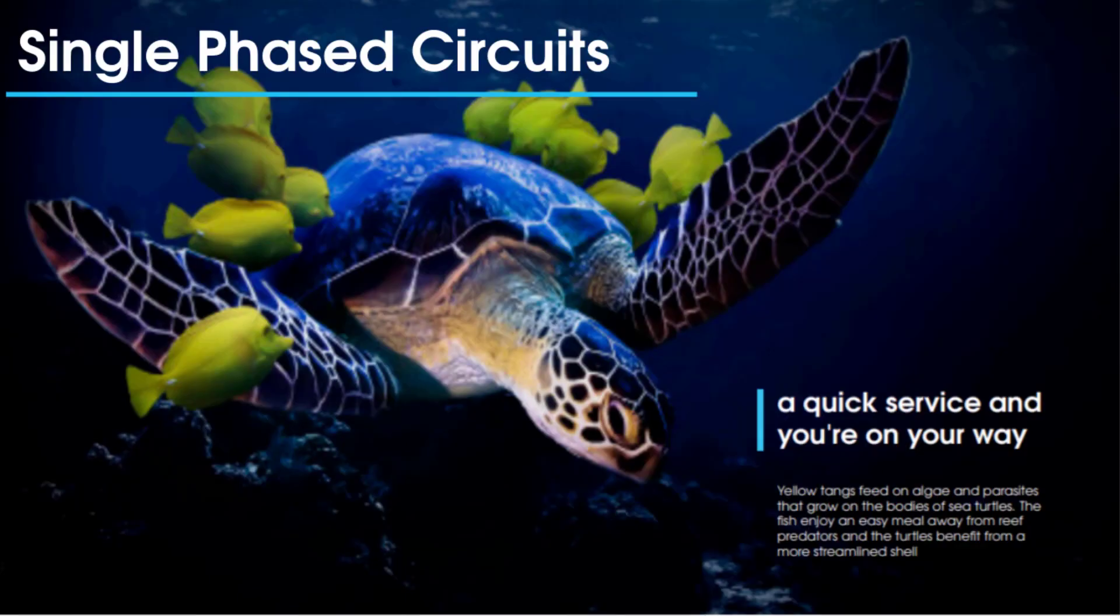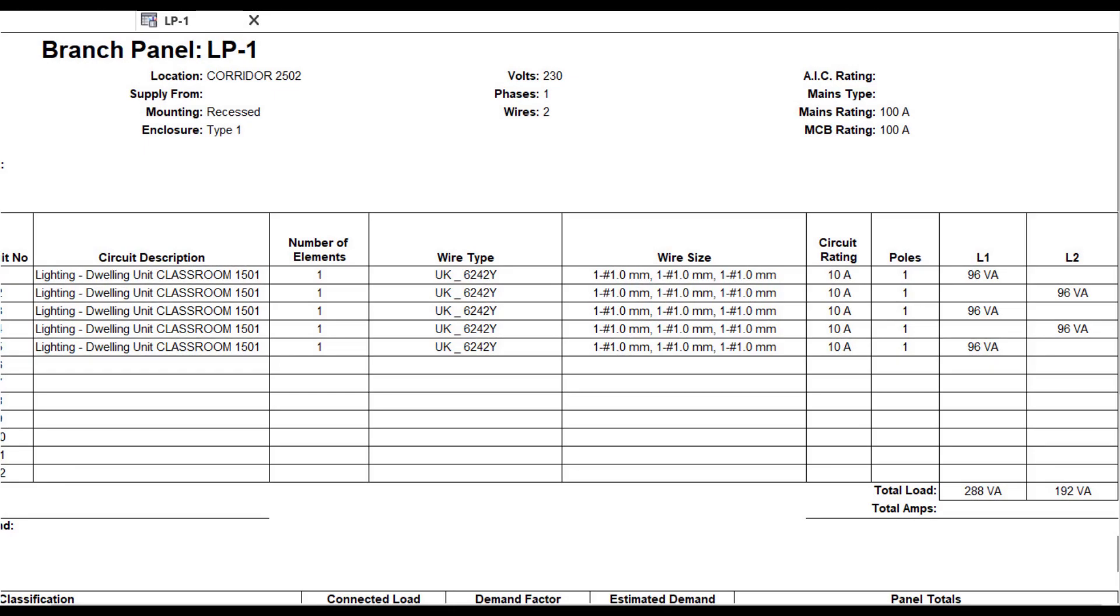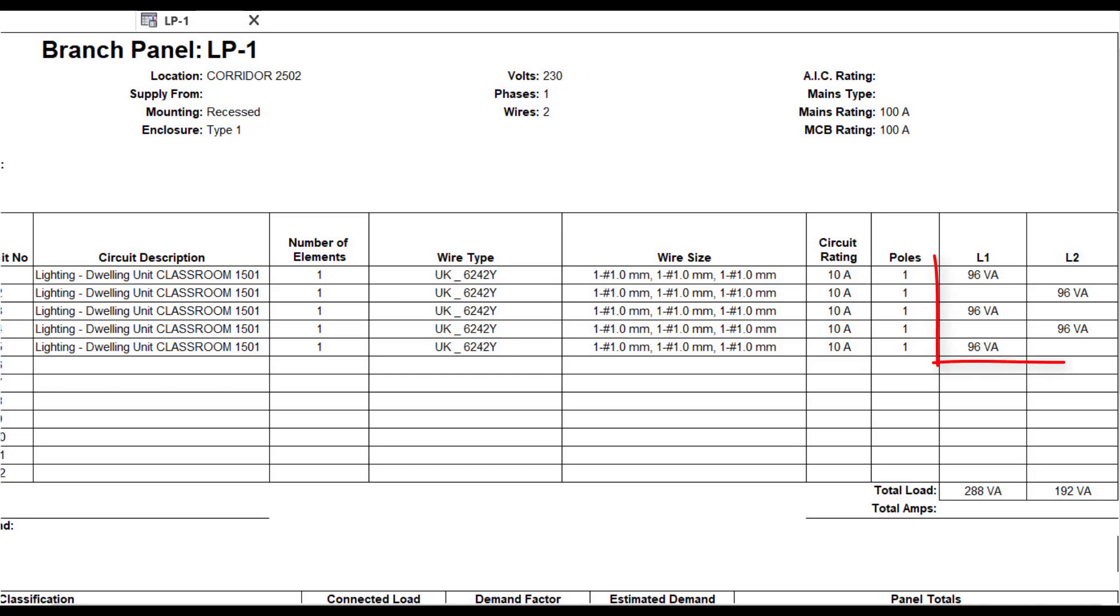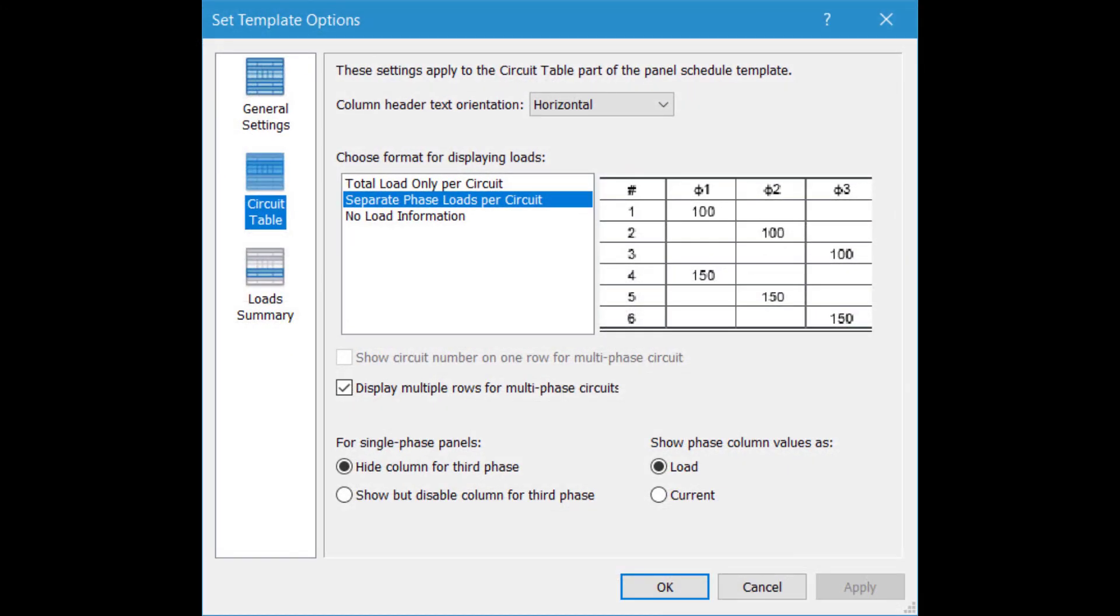Let's take a look at single-phase circuits and panel schedules. Two specific issues previously arose when working in this area. Firstly, loads connected to a single-phase board would show as being connected across different phases on a panel schedule. Here we see the loads connected across two phases. Secondly, there was no allowance in panel schedule template options to show only the phase the loads were connected to. The settings only catered for hiding or disabling the third phase.